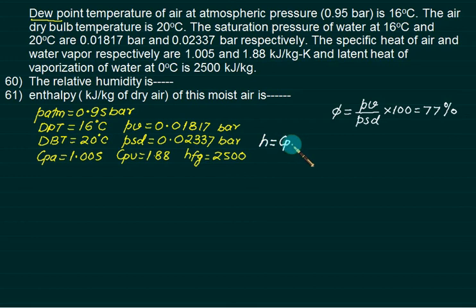Calculation is for enthalpy. Enthalpy is CP of air multiplied by dry bulb temperature plus your HFG value plus CP of vapor multiplied by dry bulb temperature. This whole value is multiplied by W. This one is water contribution and this one is air contribution. First of all, we have to find out W.